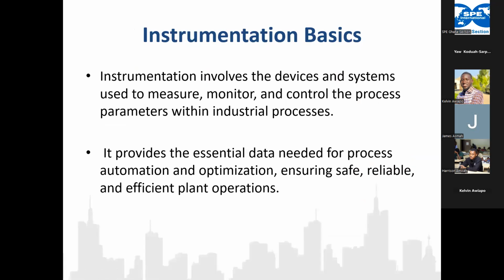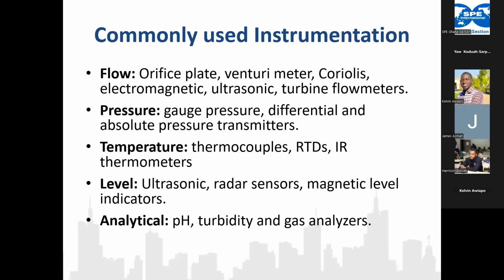Now, instrumentation is the devices and systems which we use to measure, to monitor, and to do the control. Some commonly used instrumentation, for instance, for flow: we have orifice plates, venturi meter, Coriolis mass flow meter, electromagnetic, ultrasonic, and turbine flow meters. It depends on what you are measuring at the time, the product, and even cost, and the accuracy you need at a point in time or depending on the process, and you choose whichever flow transmitter you want to use.